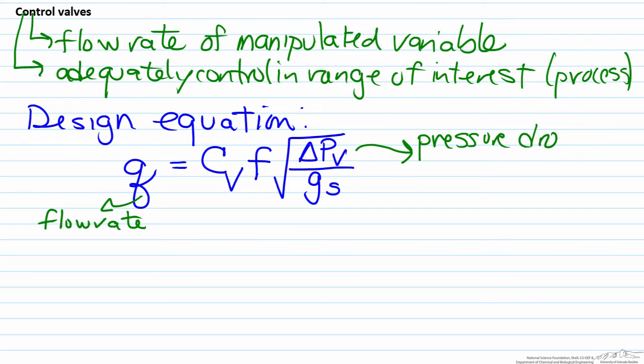Delta PV represents the pressure drop. It's not the entire pressure drop across the entire process. This is the pressure drop across the valve only, and this can become important as you are trying to appropriately size a valve. Gs represents the specific gravity.